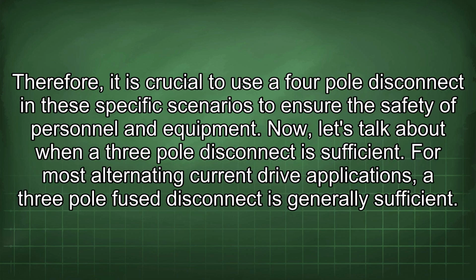Therefore, it is crucial to use a 4-pole disconnect in these specific scenarios to ensure the safety of personnel and equipment. Now, let's talk about when a 3-pole disconnect is sufficient. For most alternating current drive applications, a 3-pole fused disconnect is generally sufficient.